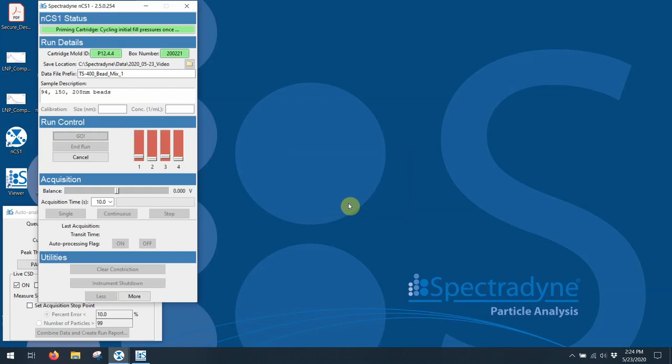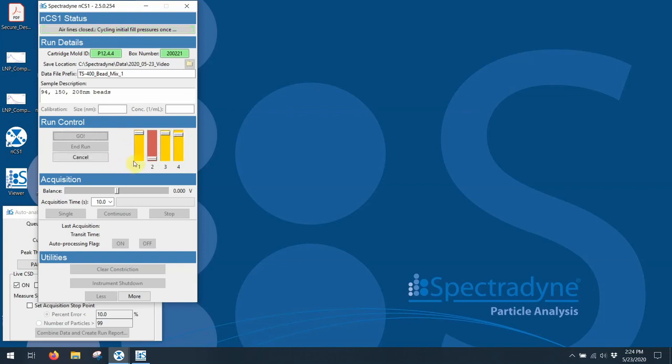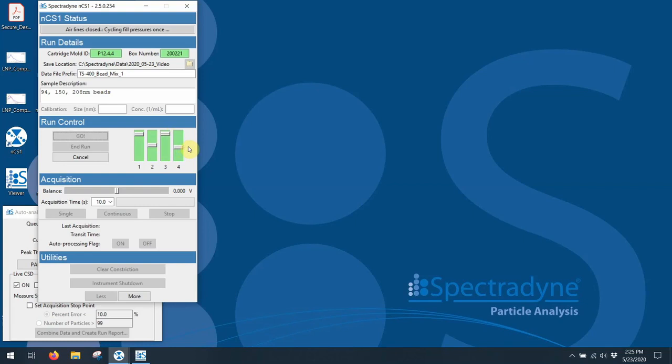The cartridge goes into the system. Basically, it's dry other than what's in the sample port. You can see here something called the fill monitors. And what these fill monitors do is they check the conductivity in different parts of the cartridge. So by watching these, I can see which parts of the cartridge are getting filled and now have conductivity. So you can see now that 1, 2, 3, and 4 all show conductivity. And 1 and 3 should be up on high like this. 2 and 4 should be in the middle like this. And as the system sees that they're there and stable, it now turns green. So this is the state we want these monitors to be in.